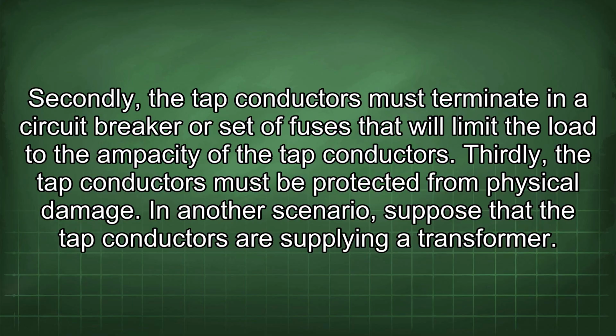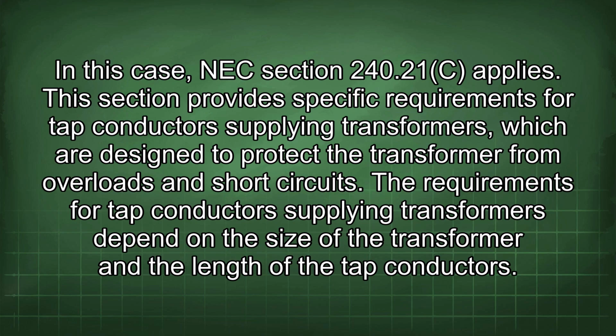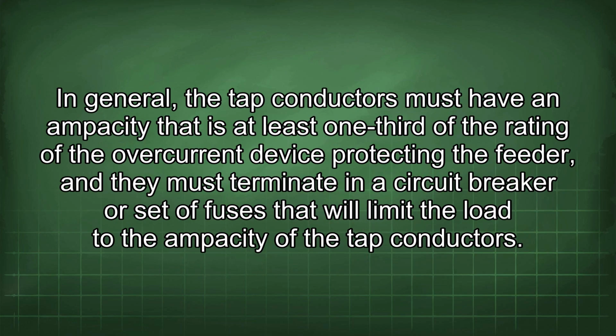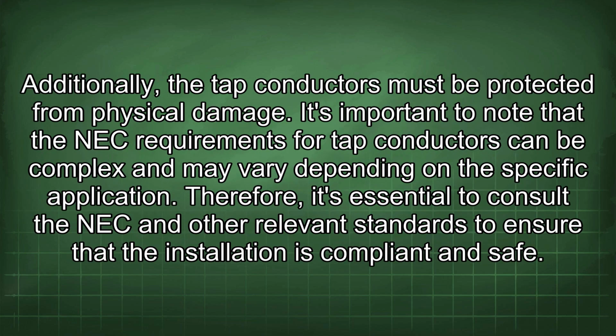In another scenario, suppose that the tap conductors are supplying a transformer. In this case, NEC section 240.21(C) applies. This section provides specific requirements for tap conductors supplying transformers, which are designed to protect the transformer from overloads and short circuits. The requirements for tap conductors supplying transformers depend on the size of the transformer and the length of the tap conductors. In general, the tap conductors must have an ampacity that is at least 1/3 of the rating of the overcurrent device protecting the feeder, and they must terminate in a circuit breaker or set of fuses that will limit the load to the ampacity of the tap conductors. Additionally, the tap conductors must be protected from physical damage.